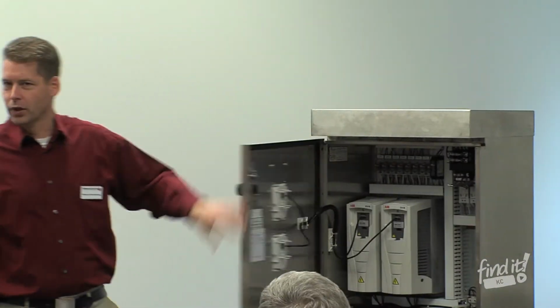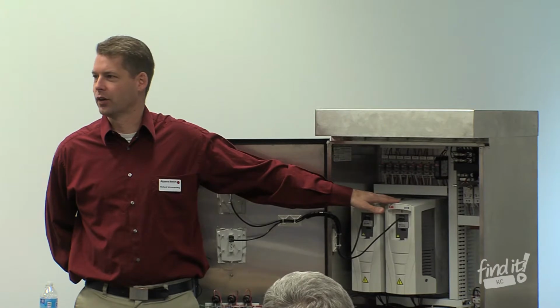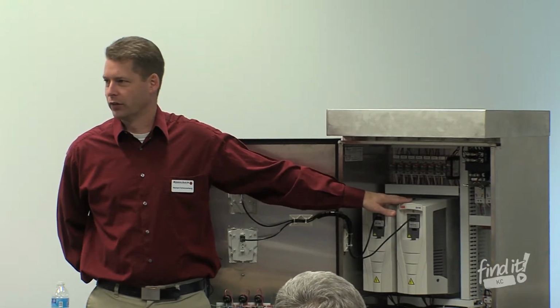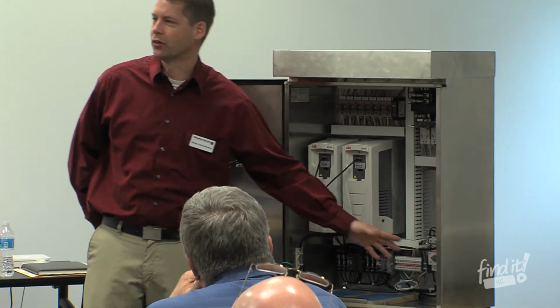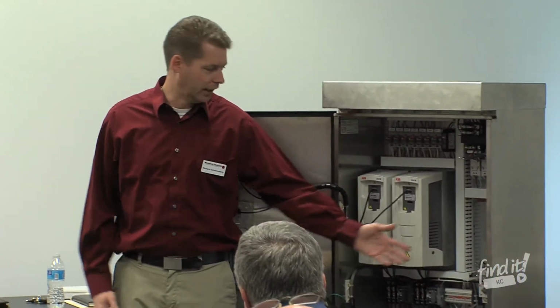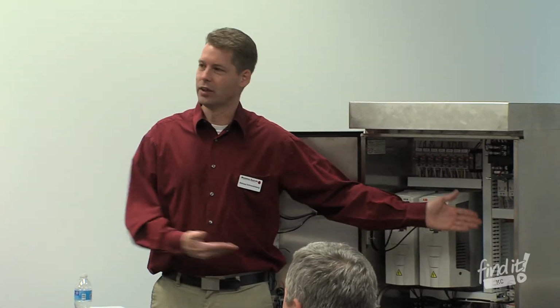And the answer is yes. It's been fairly well thought out. It's a fairly mechanical solution. You can actually see it here. This is a redundant VFD solution, but it could have been one VFD instead. But you'll see down here I've got 3 motor manual circuit protections going on here. So each motor has its own overload protection. And in this case, it also has an automatically tripping device, a manual motor protector that turns off. If that one motor starts to overamp, it'll shut that one off, leaving the other 2 to run.